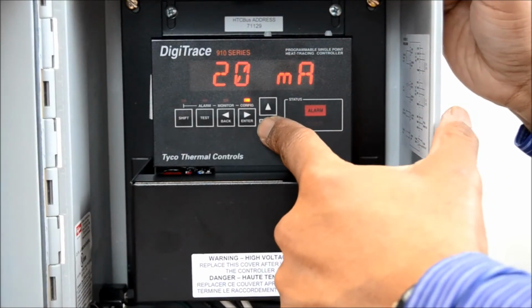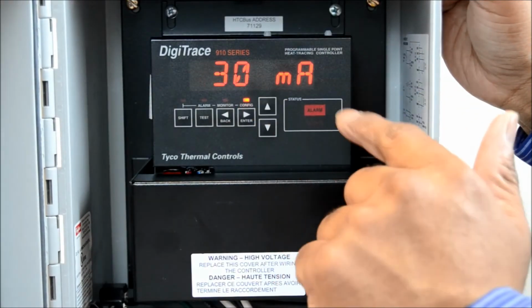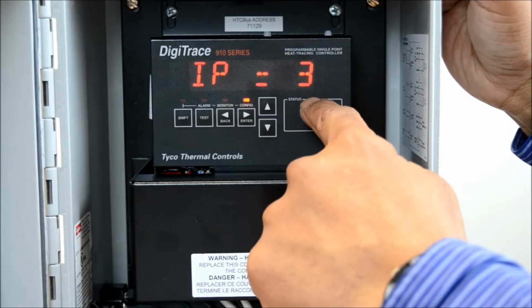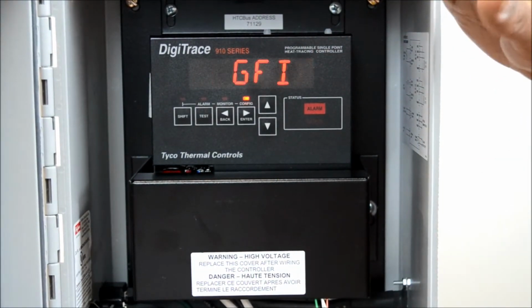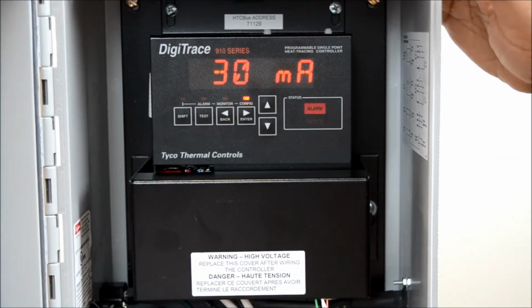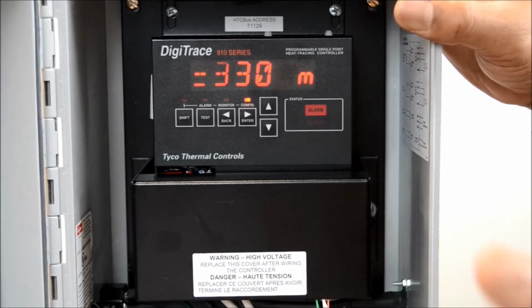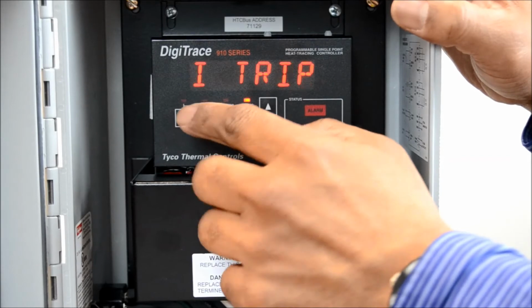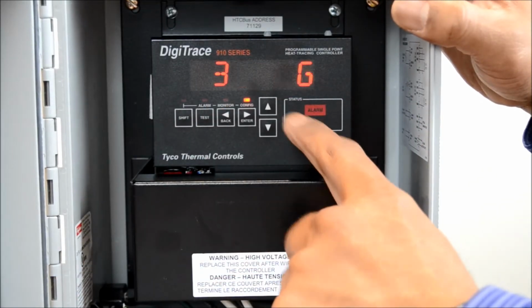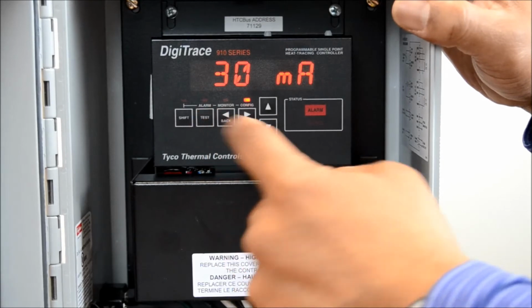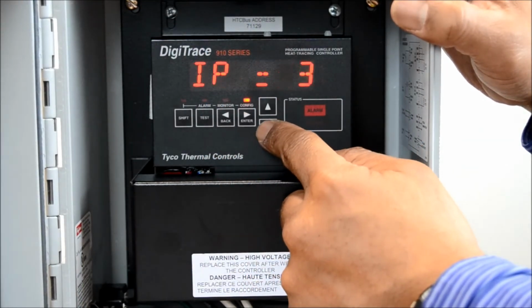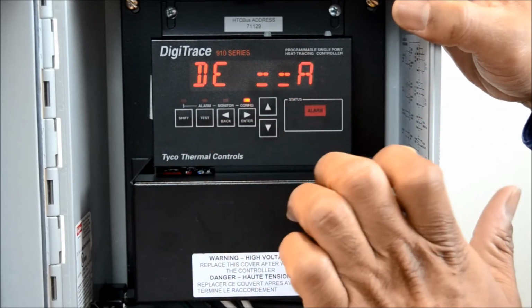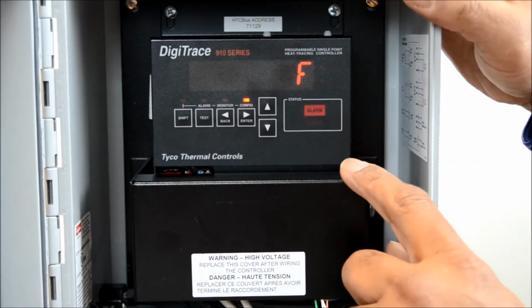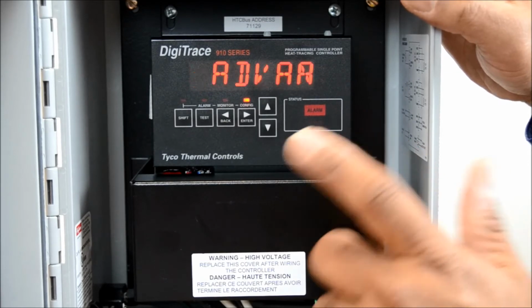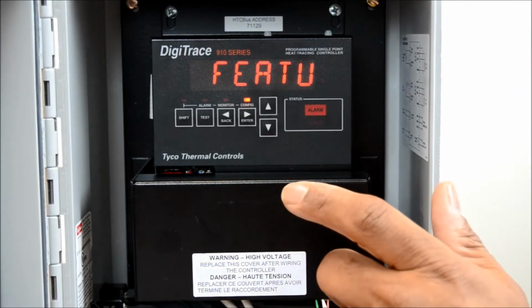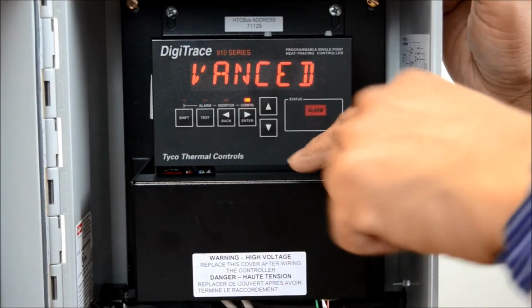Now the next feature down is the actual GFI trip feature, which is at 30 milliamps. At 30 milliamps, this is set to trip, so this will cut the heat trace off, and that's the ground fault trip. In order to clear this, and I'll talk about this a little later, you have to fix the ground fault before this will clear, but I'll talk about that when I talk about alarms. Going further down, you have feature mode, which currently I'm in the advanced mode. You have an advanced and you have a basic. The basic is basically the items that I just showed you before.